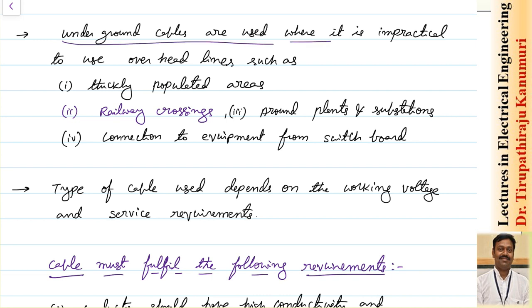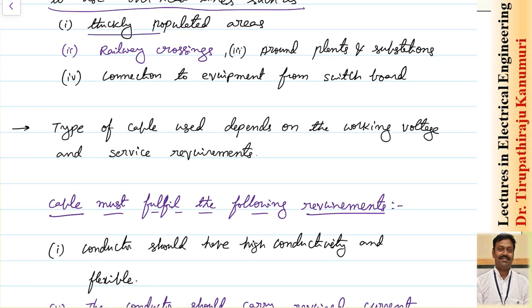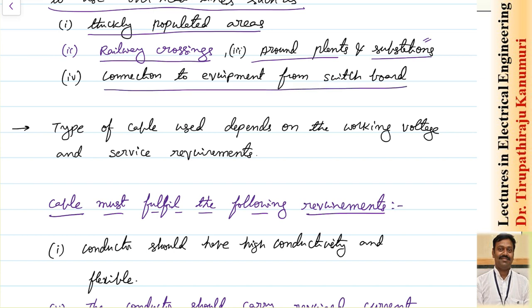Underground cables are used only where overhead lines are impractical, since overhead lines are much cheaper. Examples include thickly populated areas where sufficient clearance cannot be provided, railway crossings where an already electrified line makes overhead lines infeasible, hydroelectric power plants where power generated at 30 kV or 20 kV is transmitted to a nearby substation, and inside substations for connections to equipment from the switchboard.